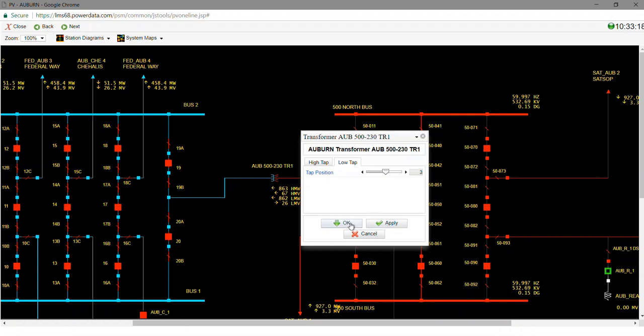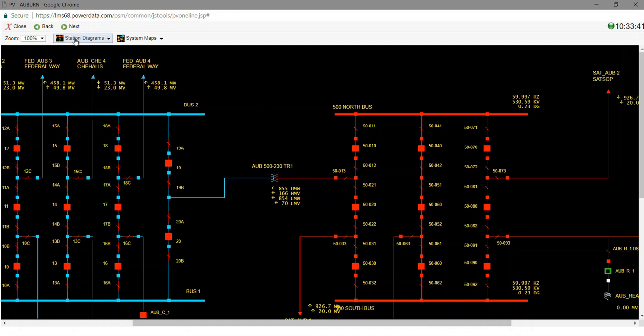The difference between OK and apply is OK will implement the change but close out the window, whereas apply will implement the change but leave the window open. So you see, as soon as I hit that, it initially reverted to its original value, but then came back to the value that I set it to. And so that is how you work a manual tap changer.